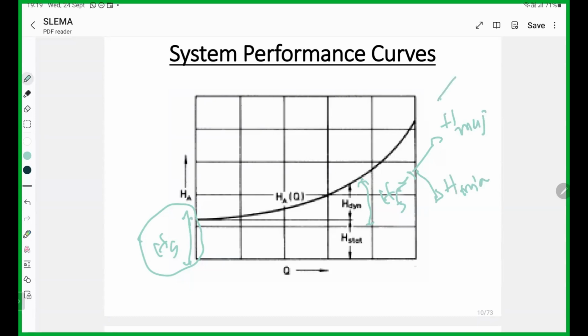Major means pipe friction. Minor means components like valve, bend, something like that. Then we have these two components. How to reduce this major part? We can definitely reduce it by increasing the pipe diameter. If the diameter is higher, then friction is less. Then you can reduce your system head if you select a higher diameter. Then you can see what the limit is.